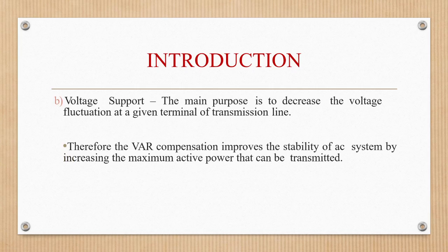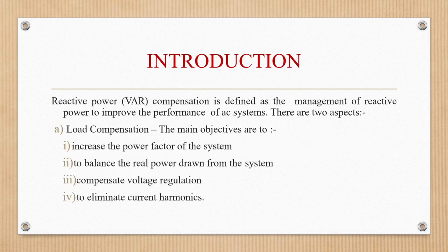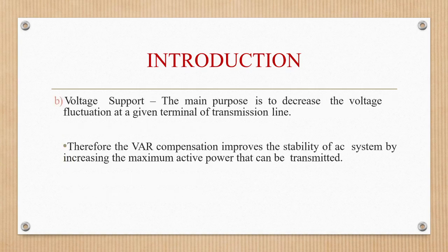For voltage support, the main purpose is to decrease the voltage fluctuation at a given terminal of the transmission line. Therefore, VAR compensation improves the stability of the AC system by increasing the maximum active power that can be transmitted. By improving power factor, balancing power drawn, compensating voltage regulation, removing harmonics, and decreasing voltage fluctuations, the stability of the system will be increased and maximum active power can be transmitted.